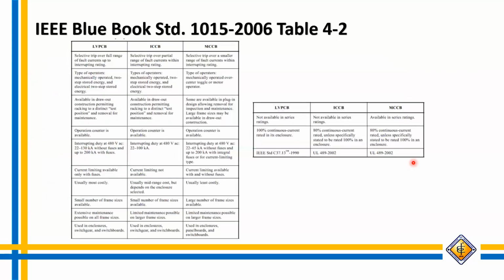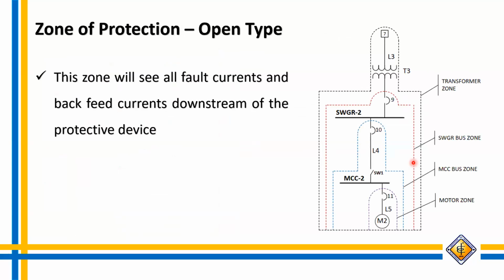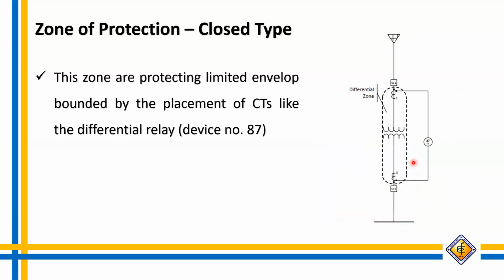So ICCB, I have not discussed that. You can just read it, so we can proceed with the calculation and manual plotting. IEEE Blue Book Standard 1015 gives the comparison between the low voltage power circuit breakers, ICCB and MCCB as well. So we have the types of protection. We have an open type. This type of protection, or zone of protection, will see all fault currents and backfeed currents downstream of the protective device. We have also the closed type, meaning this zone protects a limited envelope, like the differential relay.